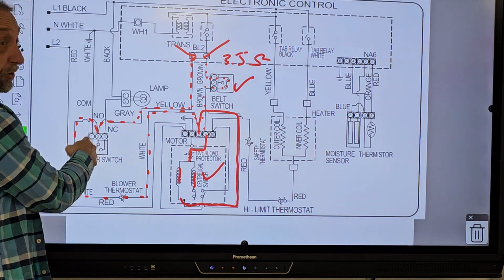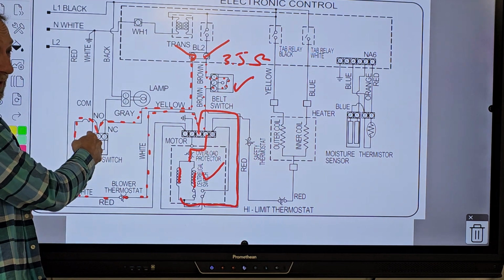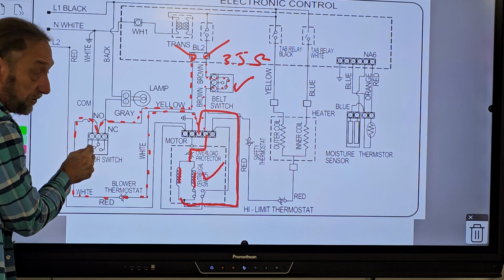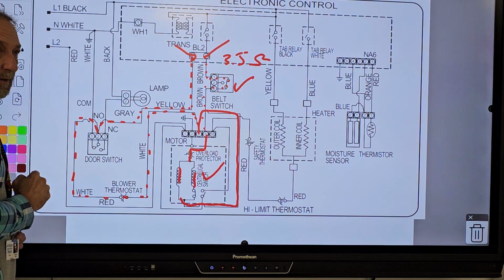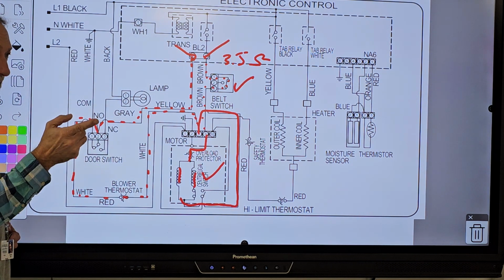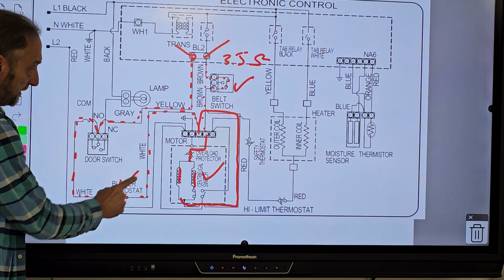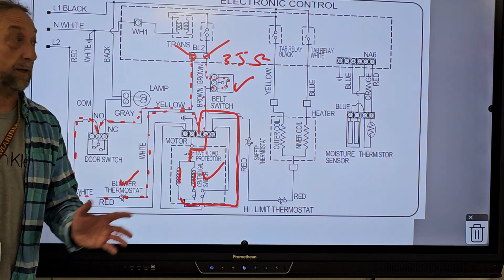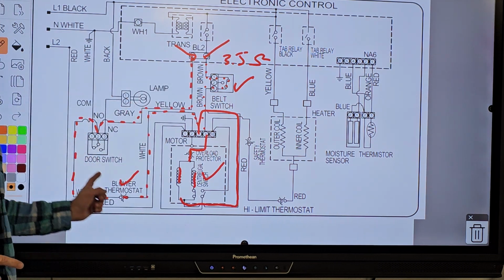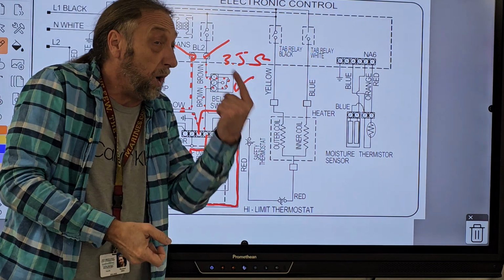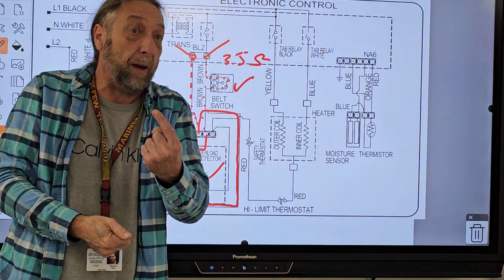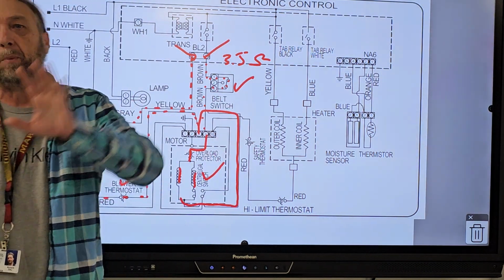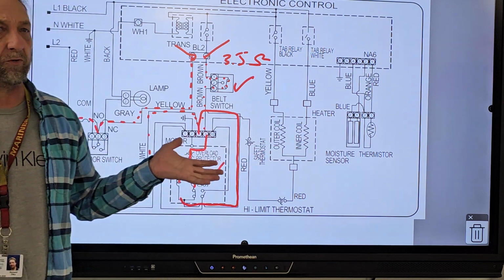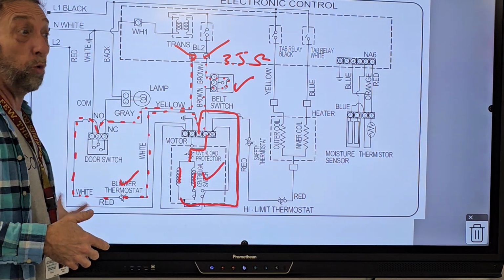Well, we're not actually going through the door switch — the wire goes to it and jumps right back, it's not going through the switch. Okay, what else? Blower thermostat. Okay, if I got a reading here, all those parts are good. Now if I didn't get one — if I don't get a reading, one of them could be bad, but now I know I've got to check each one. But we had a reading of about 3 or 4 ohms, so that told me that whole circuit's good.